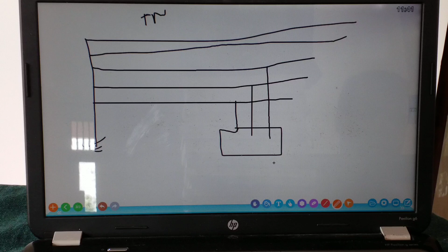Okay, then what is TN? In TN, this is my transformer. It may be earthed or not, but it should be earthed. Phase 1, phase 2, phase 3, neutral, and I am also giving an earth. If I am the customer, I take earth, neutral and phase from my utility source. Here not earthed, here earthed. We call it the TN system. And also we call it TNC system. Sorry, TNS system.